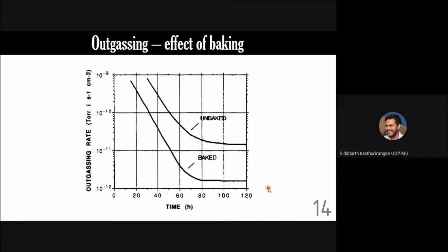Another idea which I'll mention, there is no slide on that, is about whenever you are breaking the vacuum. Suppose you want to change a component inside the accelerator system, then you have to break the vacuum completely, open it, do the modification which you need, again close it, and again pump out all the air. The venting, that is the initial inletting of gas to bring the vacuum system back to atmospheric pressure, many times uses nitrogen gas instead of air, and on rare occasions argon gas.